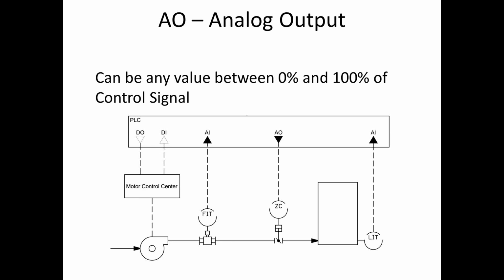And an analog output is the same way. Sending a 12 milliamp signal out to that valve may be telling the valve that it needs to open halfway. If you look at the whole system in particular, you'll see that the flow indicating transmitter is sending an analog signal into the PLC. The PLC is comparing that and saying that maybe the flow isn't up to set point, and you need more flow. So it's going to send an analog output to the valve, telling the valve to open up a little more to allow more flow to go through, and that will fill that tank up.